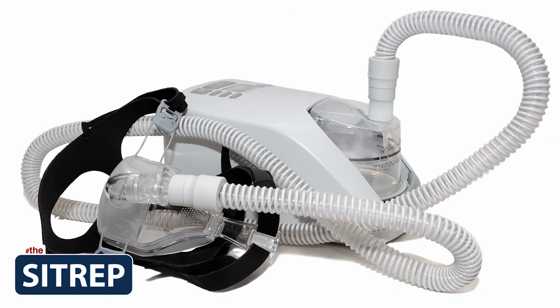And how that works is you put an interface on with the CPAP, as is behind me here, and it blows air into the airway to open up that airway that I told you closes. Now, we usually set the machines on an auto PAP, which means we set it, say, 6 to 16. That's what we do here, which means that we'll set what they call a ramp, and that will give you about 20 minutes to get to sleep. So for the first 20 minutes, it'll blow at like 4 centimeters of pressure. After that, it will determine how much pressure it needs to blow to open up that airway. And it can go anywhere from 6 up to 16 centimeters of pressure.